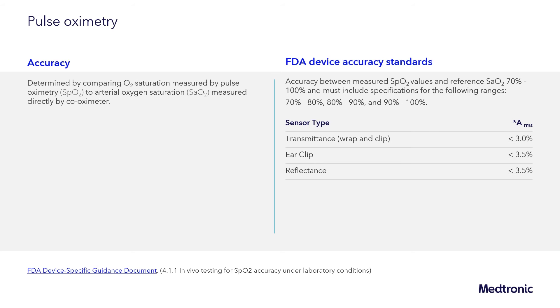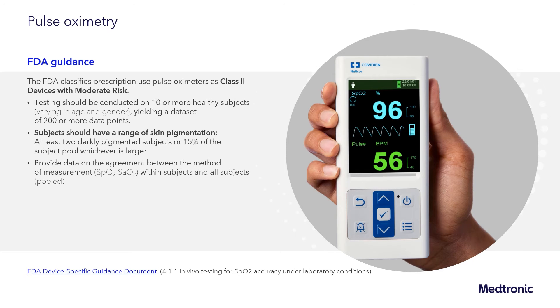The FDA classifies prescription use pulse oximeters as a class 2 device with moderate risk. The recommendations for testing of these devices in development require that testing should be conducted on 10 or more healthy subjects in varying age and gender, yielding a data set of 200 or more data points. Those subjects should have a range of skin pigmentation, at least two that are darkly pigmented in the group of 10, or if the sample size is larger, 15 percent of the subject pool. We must also provide data on agreement between the method of measurement — the difference between SpO2 and SaO2 — within those subjects and all subjects that are pooled.